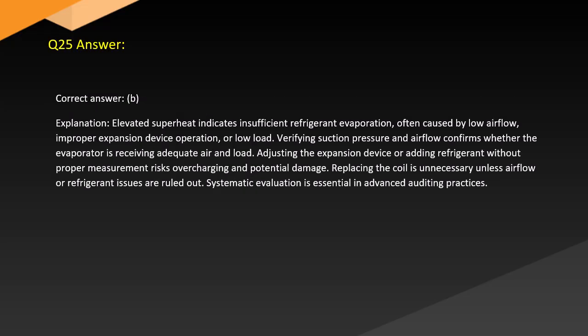Answer. Correct answer. B. Explanation. Elevated superheat indicates insufficient refrigerant evaporation, often caused by low airflow, improper expansion device operation, or low load. Verifying suction pressure and airflow confirms whether the evaporator is receiving adequate air and load. Adjusting the expansion device or adding refrigerant without proper measurement risks overcharging and potential damage. Replacing the coil is unnecessary unless airflow and refrigerant issues are ruled out. Systematic evaluation is essential in advanced auditing practices.